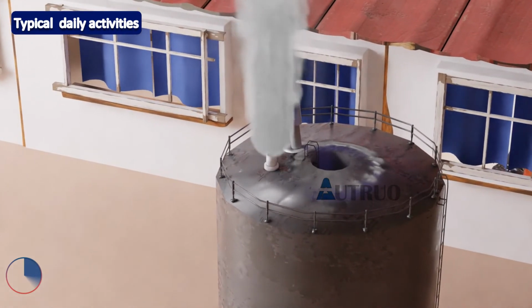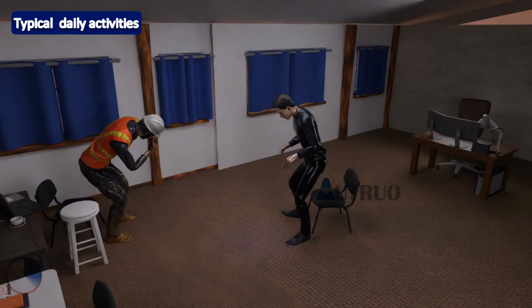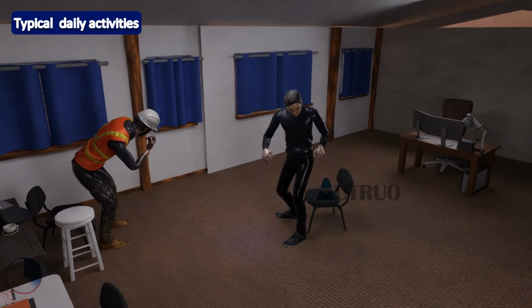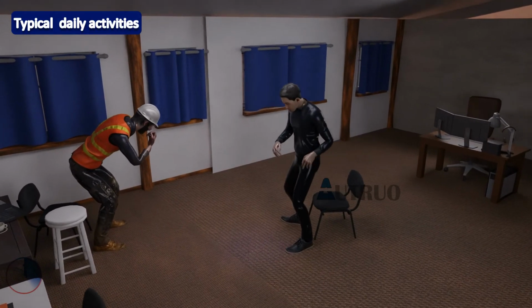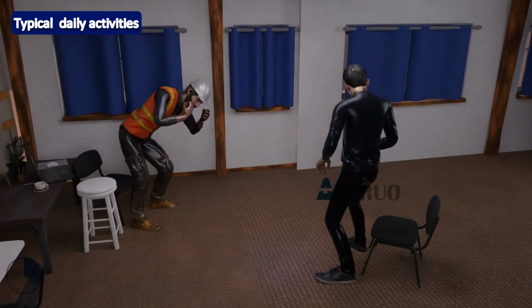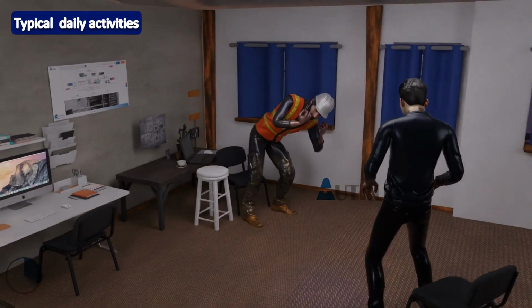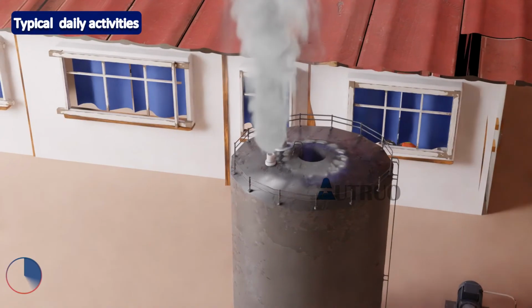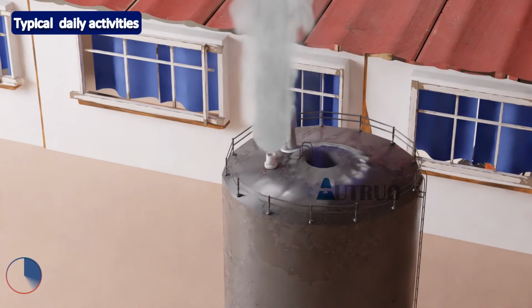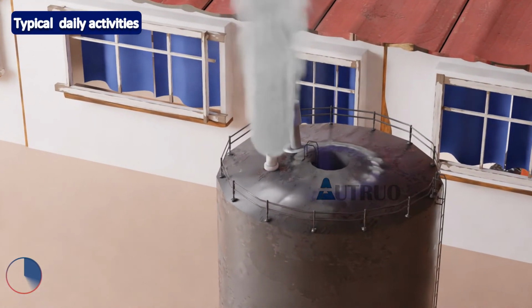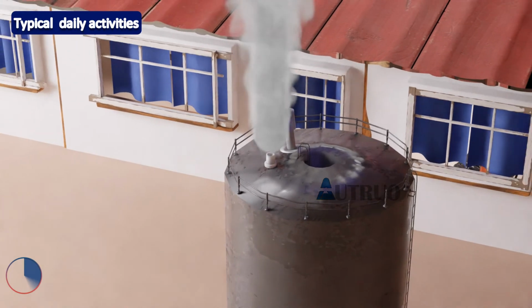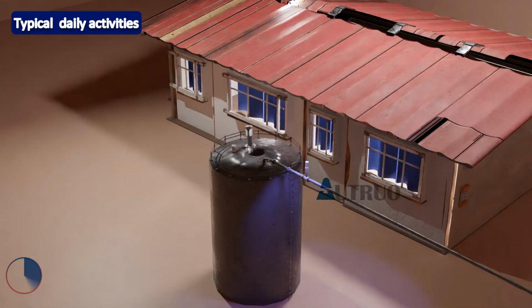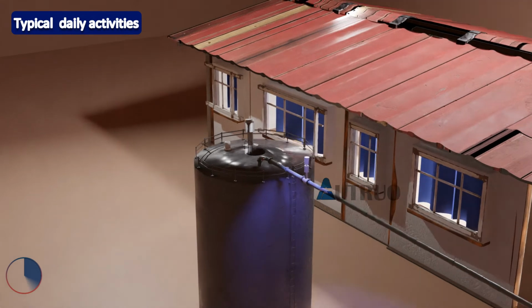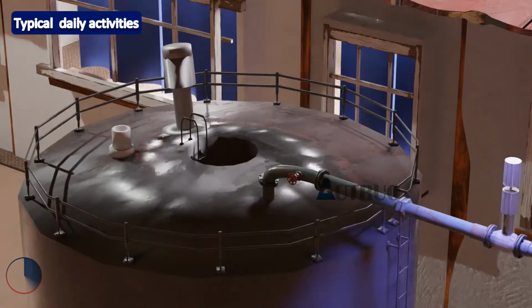What is that? It sounds like a sudden depressurization of gas. Could it be the process tank? It better not be. There is need to investigate. The quick exhaust valve is active. No wonder the venting sounds. But the modulating valve is meant to open at varying range in response to the pressure within the tank.